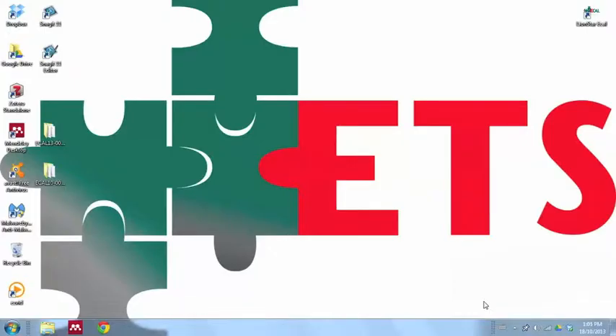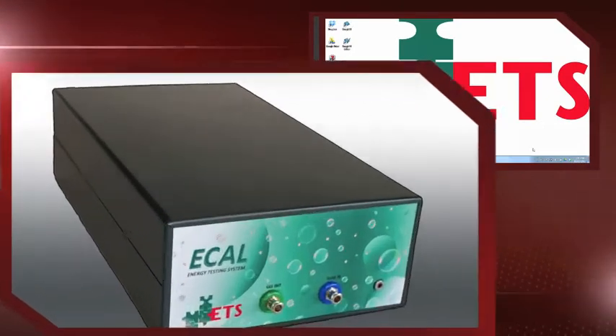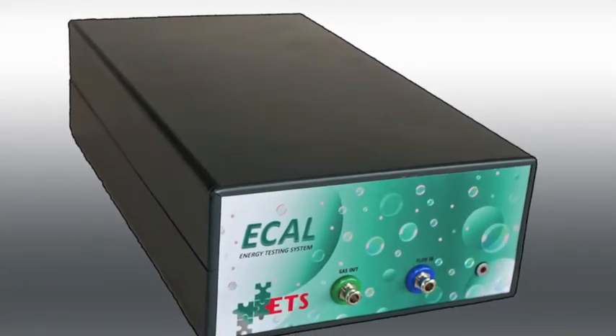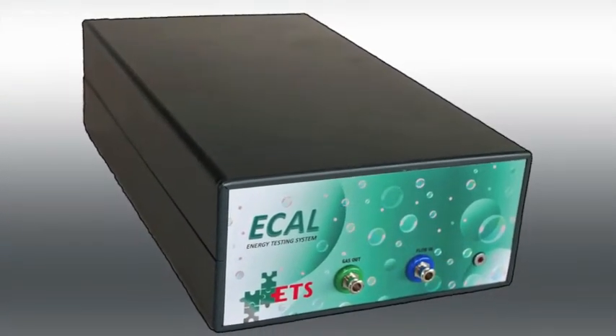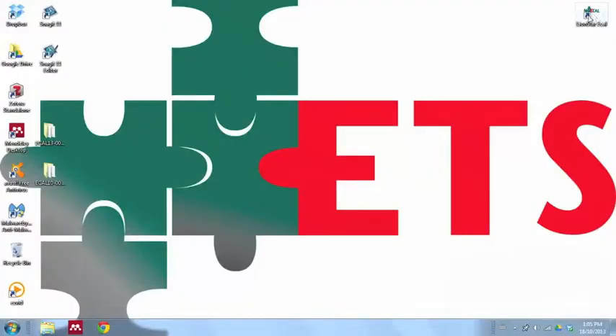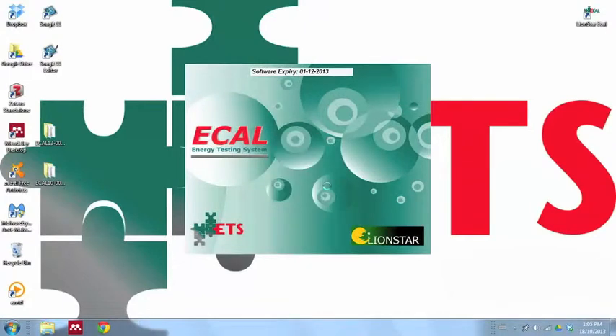However, if the device has been switched off, please ensure that it has been on for at least 15 minutes before using. Also, ensure ECAL is connected to the computer via USB cable. No gas lines should be connected at this stage. To commence testing, click the ECAL icon to open the software. When the reference number of the connected ECAL appears on screen, click OK.